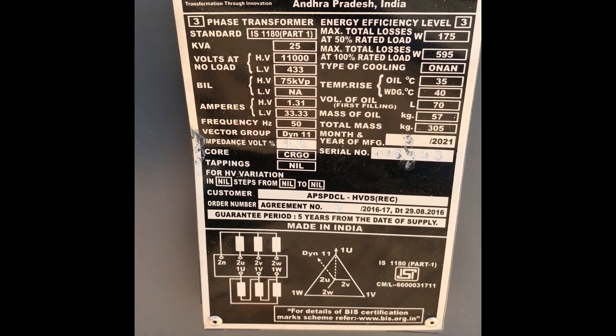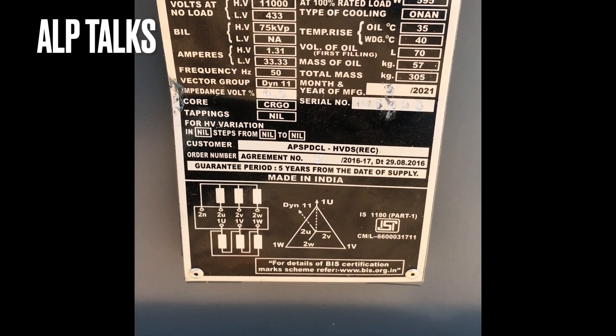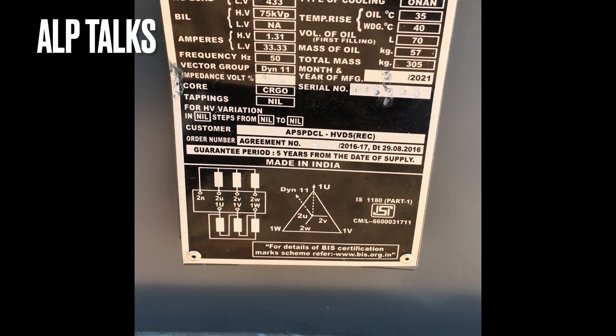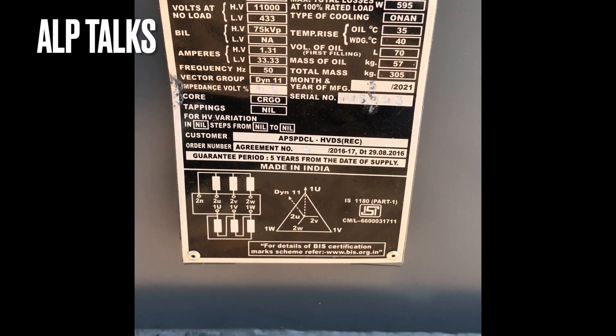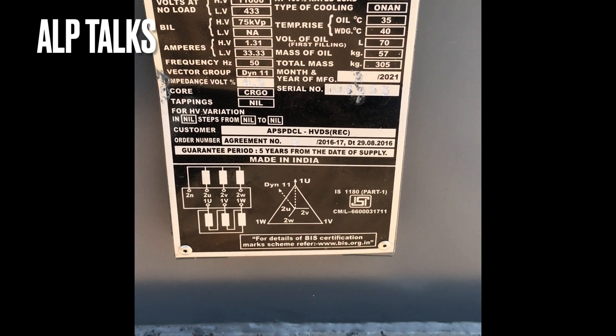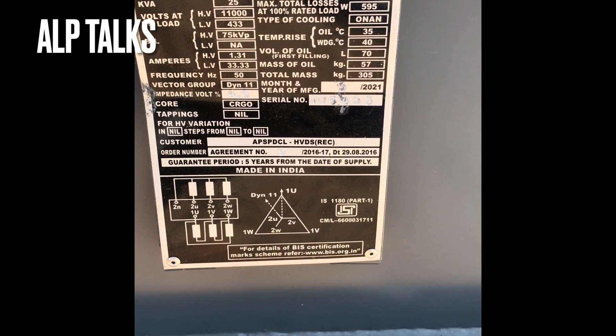We have a 25 kVA, 11 by 0.433 kV transformer. The HV side is 75 kV peak with a current of 1.31 amps, LV side is 33.3 amps, frequency is 50 hertz, vector group is Dyn11, and it is of CRGO core. There are no taps on this transformer. The 50% losses are 175 watts and 100% losses are 595 watts. The cooling is ONAN.